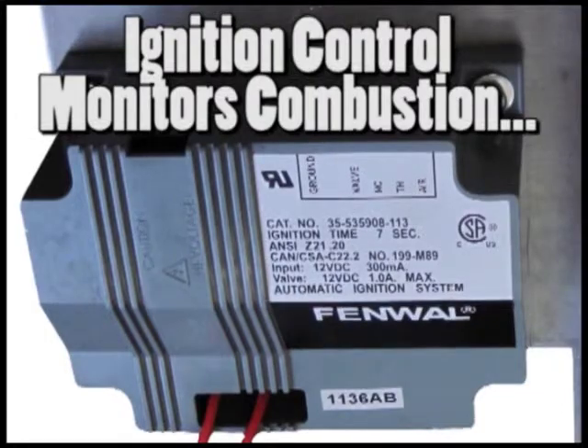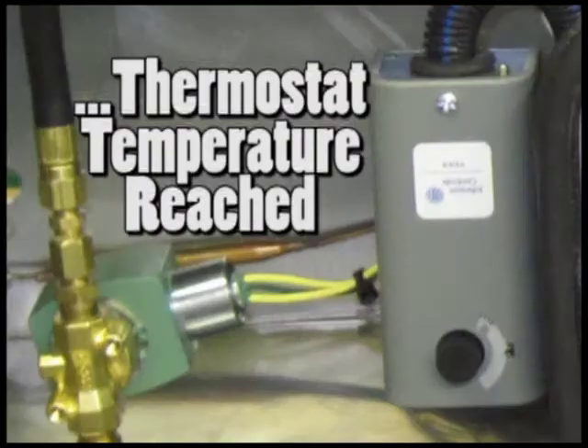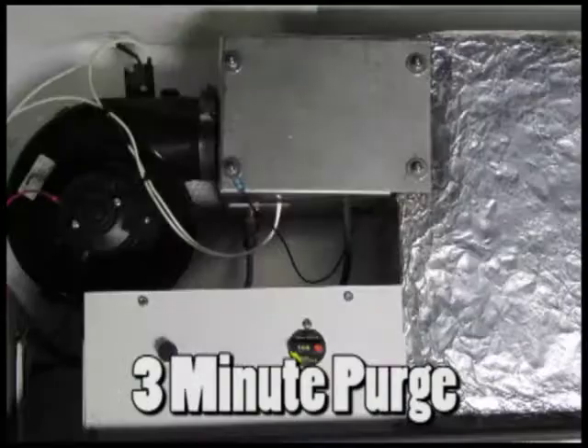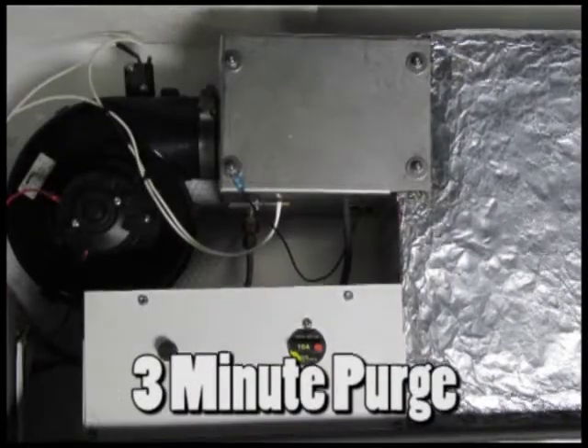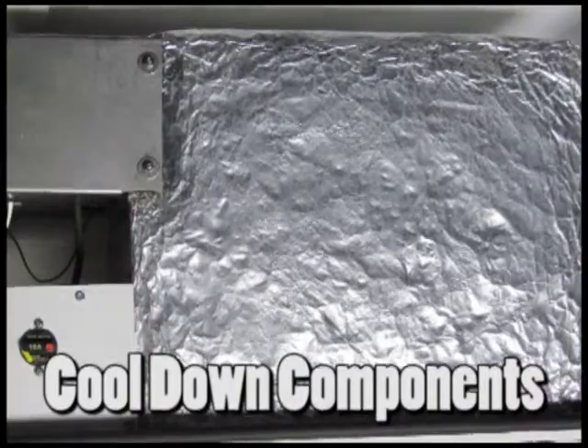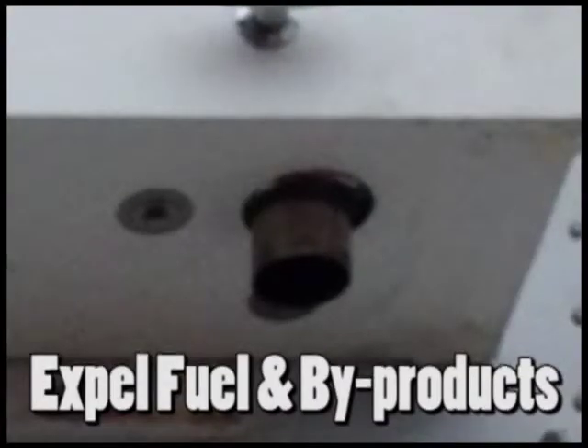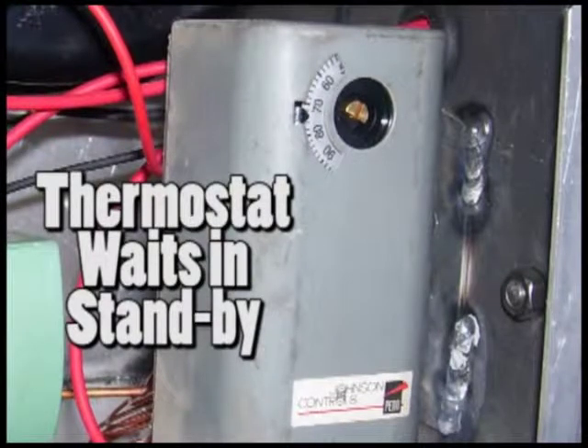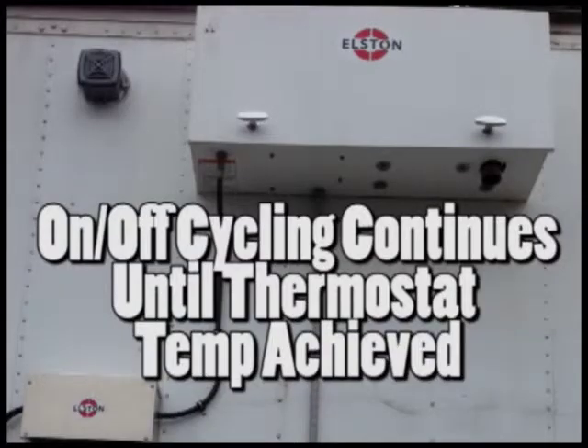Once started, the ignition control will monitor combustion until the thermostat temperature is reached. When thermostat temperature is achieved, the heater will perform a 3-minute purge that will cool down heater components and expel any unburnt fuel and exhaust byproducts. The heater will wait for the thermostat to activate again in a cyclical action. This automatic on-off cycling will continue as many times as necessary to maintain the thermostat temperature.